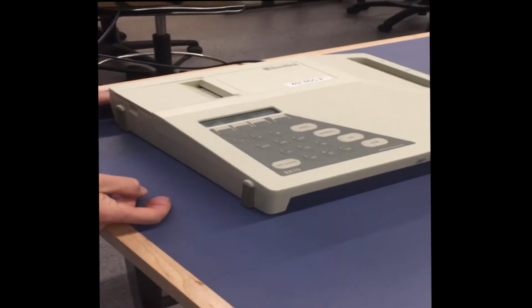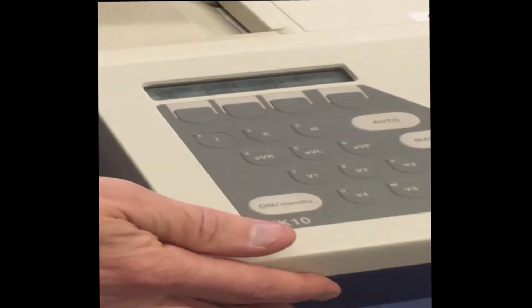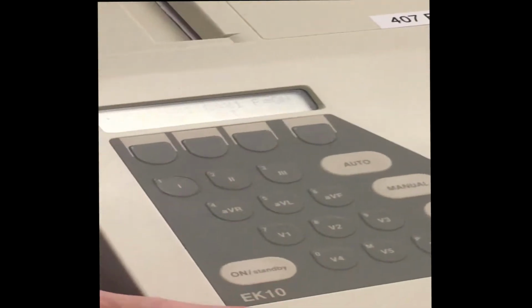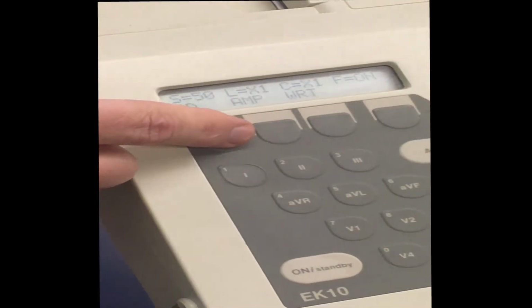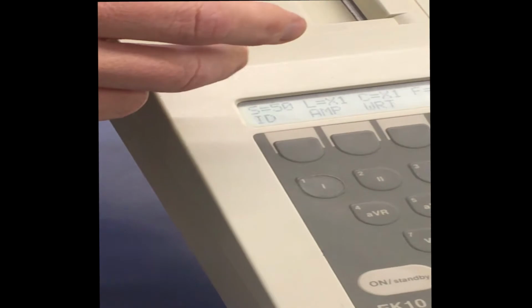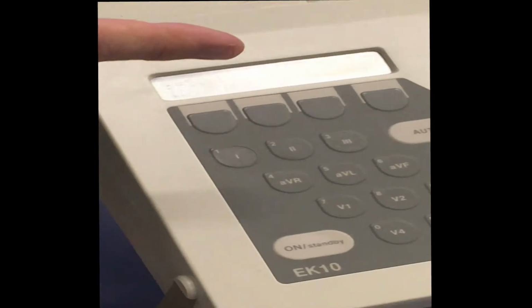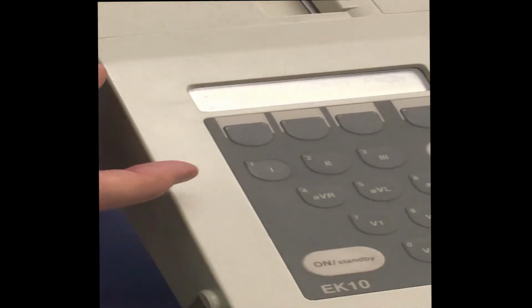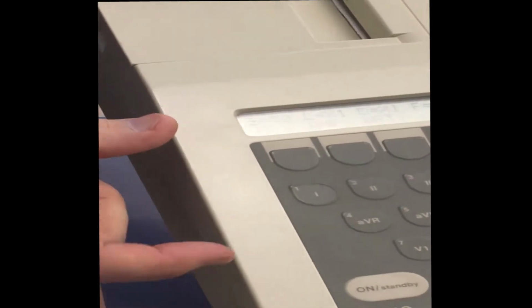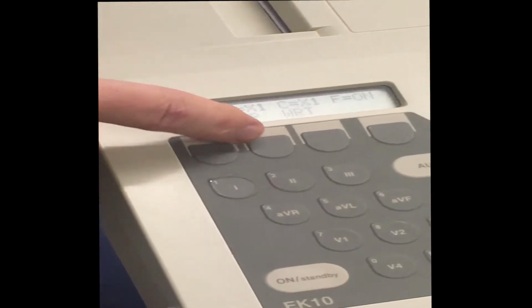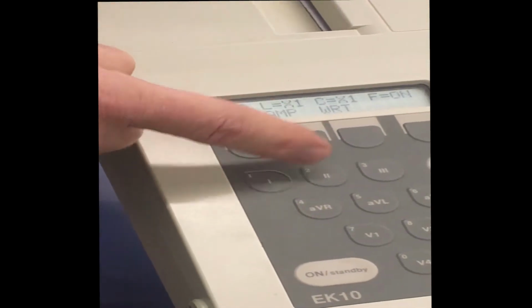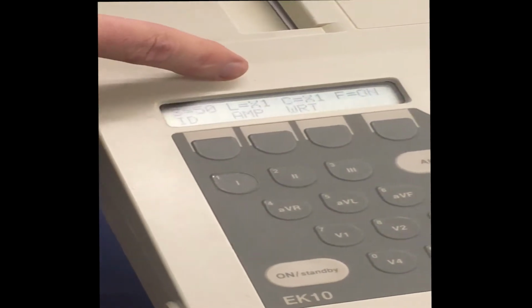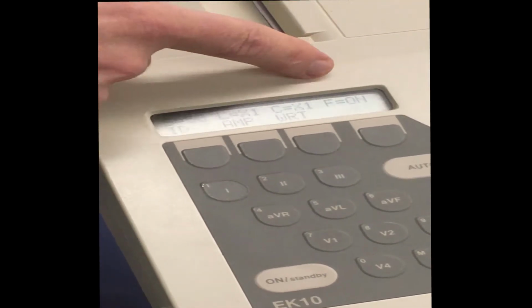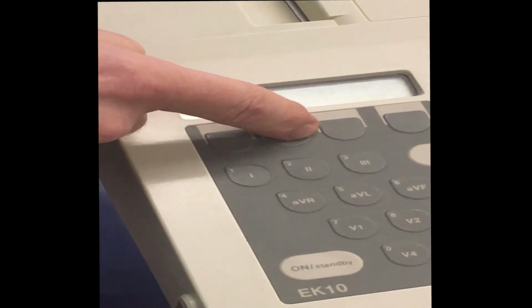If I want to change those, it's relatively straightforward. The first number is ID. So if I press this number, I could put in an ID number, and when you would use that is if you had subjects with different ID numbers. We're not going to use that because you know who your subject is going to be. The next button says AMP. So if you press that button, it allows you to change the limb gain, the chest gain, and the filter. So I'm going to press this AMP button.